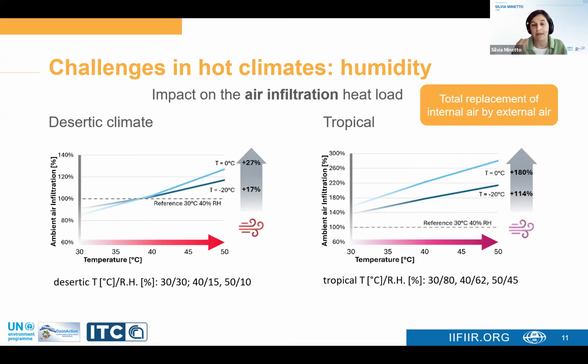So if we stay on the left graph, in a desertic climate, there is actually an increase in the air infiltration load if we move from 30 to 50 degrees, but it's quite limited, and this is because the air is very dry. But if we go to a tropical climate, and this is described in the right graph, then the situation can become very complicated, because if we move from 30 degrees to 50 degrees, with respect to the design condition, which was 30 degrees, 40% relative humidity, considering that at 50, we have assumed 45% relative humidity, we have an increase in the thermal load, which can be as high as 180%, which is a very huge increase in the thermal load.